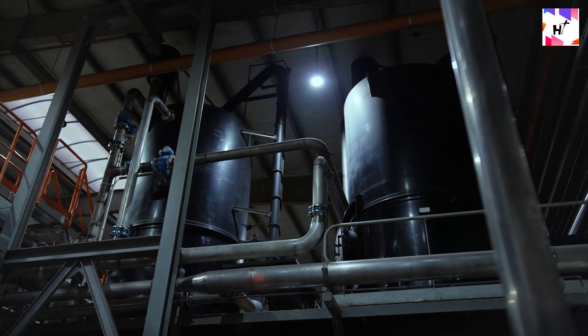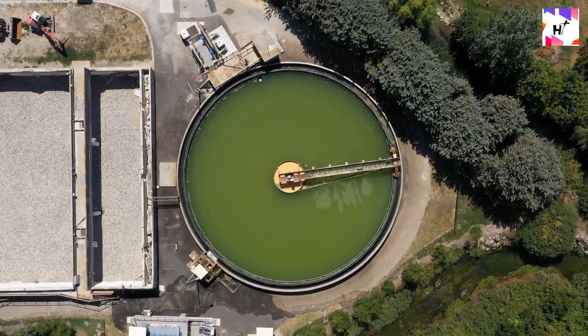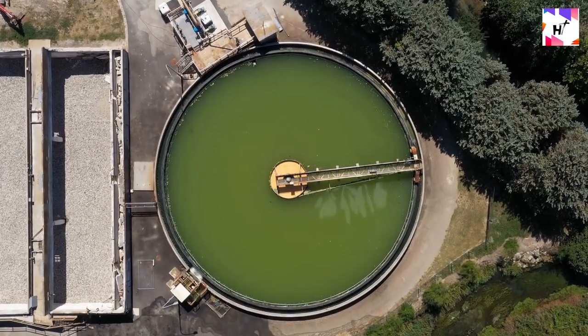The clarifier compartment frequently has slanted sides and is of the hopper style. Sludge is directed into the suction side of the airlift tube by these sides, which also prevent it from adhering and stacking up. The sedimentation tank's bottom-dwelling untreated sludge is pushed back into the biofilter reactor, where it is once more broken down by microorganisms.